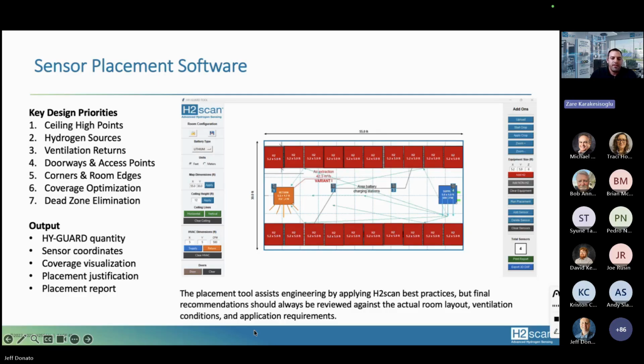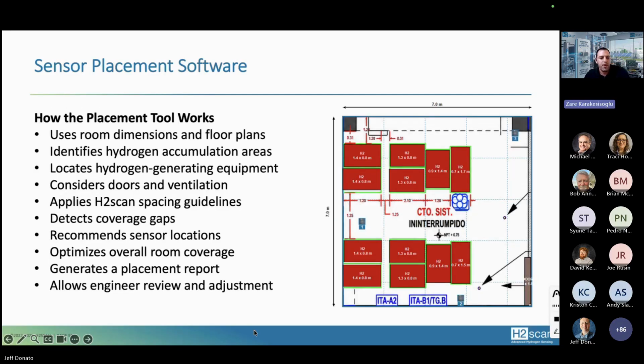The software uses room dimensions and floor plans, identifies hydrogen generating equipment, considers ventilation and access points, applies H2scan spacing guidelines, detects coverage gaps, and recommends monitoring locations. It then generates a placement report showing monitor quantity, coordinates, coverage visualization, and placement justification.